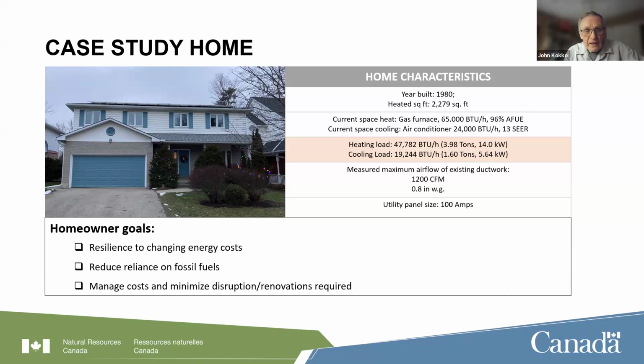Important things are what's the CFM that the actual ductwork in the house can carry at what static, and we'll get into that, as well as what is the panel size? 100 amp panel. And just to take a little diversion here for a second, one of the reasons for possibly keeping gas, other than it may be economic, is if we've got just a 100 amp panel in the house, and we don't want to have to upgrade that because it can cost a few thousand dollars. The gas backup may allow us to use a heat pump with gas backup without those extra costs.